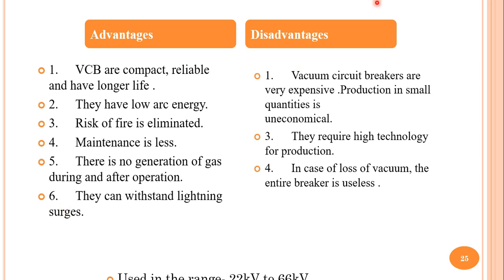The disadvantages of vacuum circuit breakers are that they are very expensive and production in small quantities is uneconomical. They require high technology for production, and in case of loss of vacuum, the entire breaker becomes useless. Vacuum circuit breakers are usually used in the range of 22 kV to 66 kV.